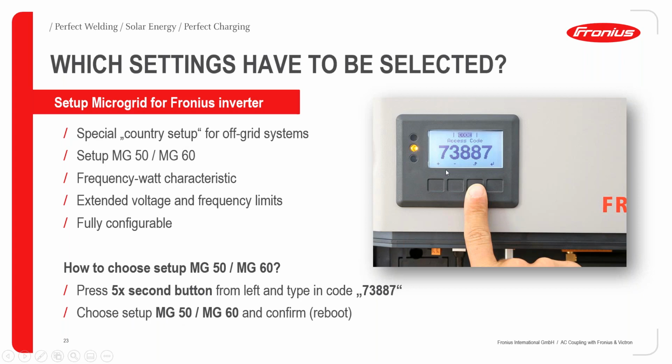I must say that I've had cases where the system didn't function properly because installers chose the normal 50 Hz. Please ensure that you choose MG50 or MG60. This will ensure that you have selected the proper code for its function in an AC coupled system in a Fronius Victron combo. Great. So once you have confirmed this, you can reboot and the system is set to go.